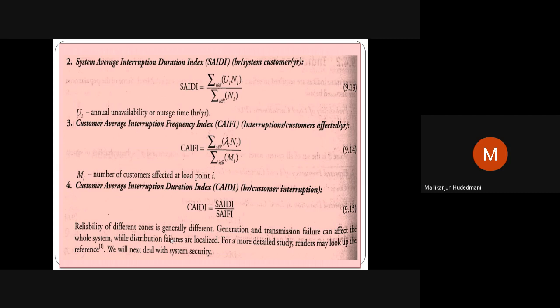Then I have the system average interruption duration. When the number of interruptions in a year is known, and I know the total interruption time in hours, if I take a ratio, it gives me hours per system customer. Like this we can see SAIDI. SAIDI refers to the sum of all i instances out of R. You can see annual unavailability or outage time in hours per year is U i for any load point n. So I sum them for all the load points, n is 1, n is 2, n is 3, up to R load points.